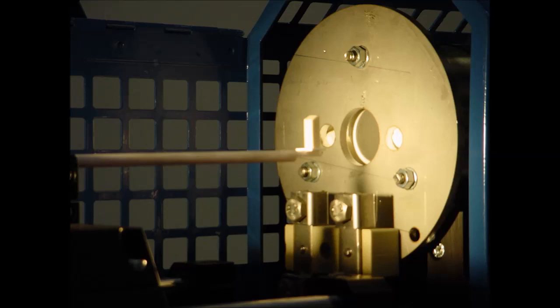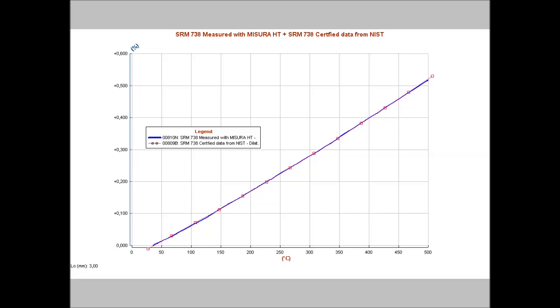The sample is introduced into a tubular kiln, which can be supplied in different versions, up to 80 degrees per minute and up to 1600 degrees centigrade. The measurement is carried out with no contact on both sides of the sample, and for this reason it is an absolute measurement. In the traditional dilatometers, the sample is contained inside the measuring system, which itself expands with temperature. When the measuring system is made with alumina, the expansion of the measuring head may be much bigger than the expansion of the specimen itself.